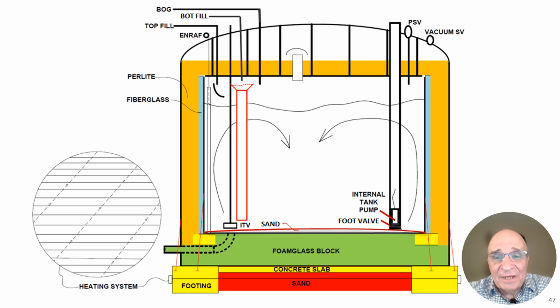So you're talking about the order of magnitude of 42 million. Are you talking 3 times that? 42, let's say 50 million. Talking about roughly 150 million pounds of force that are being held, or downward weight that's being held by this foam glass. Plus you have the weight of the metal that's associated with the tank itself.